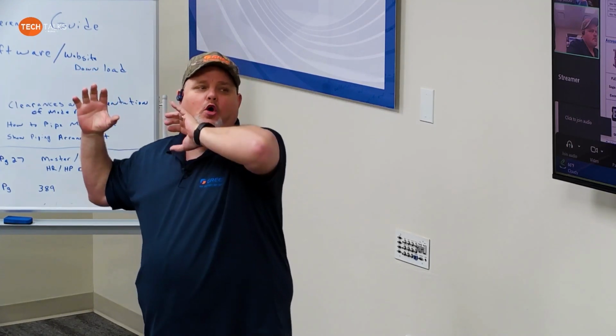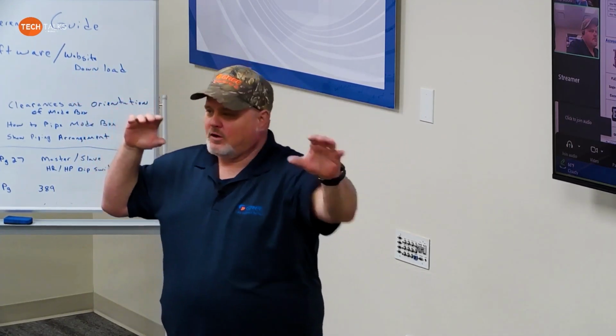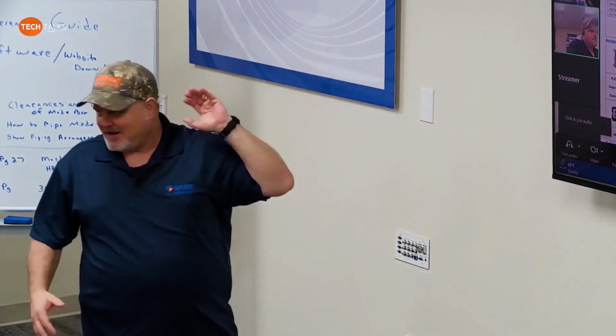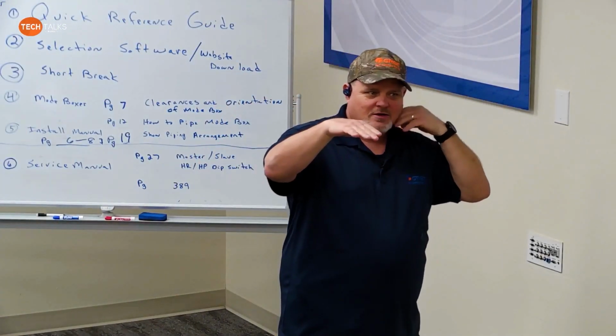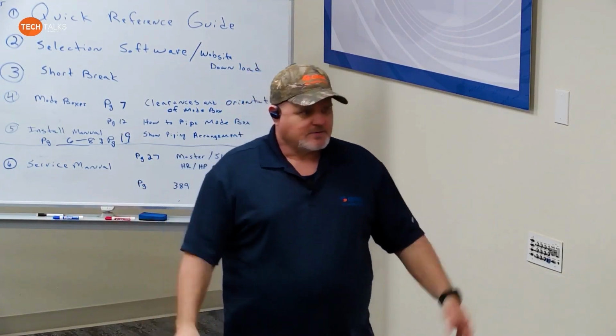It's much like sizing fuel lines, in my opinion. When you're coming off a meter and feeding a line into a building, that first pipe's got to handle the BTU capacity all the way down the line. Then once you branch off and pick up some of those gas appliances, your BTU capacity drops on the rest of the line, so your pipe can downsize until you branch off some more, then you can downsize again. It's the same thing that happens with the refrigerant: your main lines coming from the outdoor unit are going to be your biggest pipes, and as you get rid of some of that load, pipe sizes can change.